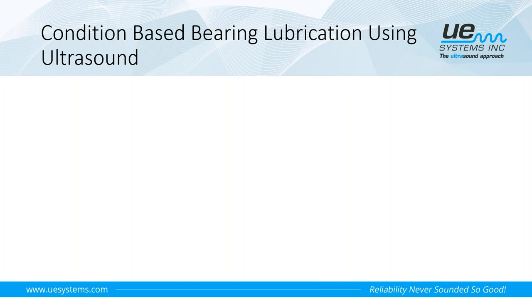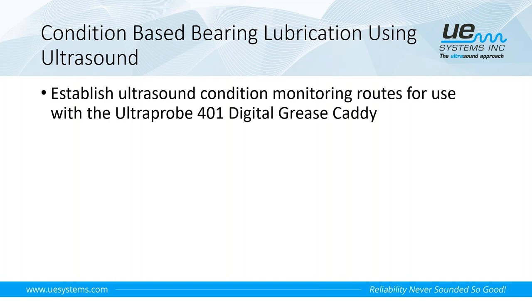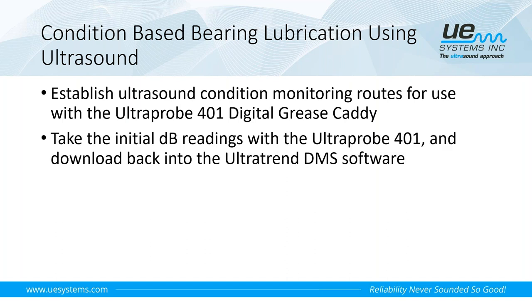Now, condition-based is going to be the best approach, and this is what you can do with the Ultraprobe 401. For those of you that have it or may have some interest, this is the scenario where you'll get the best results out of that digital grease caddy. It goes back to what we mentioned with the software, where we set up routes, and then we load that route into the grease caddy, go out and take our initial round of decibel level readings, and download that back into the software. Now, a better way to set your baselines, instead of letting the DMS software use the first reading that you download into it, is to use what's called the historical method. So we set up the route and begin to establish a dB trend or dB history on those points, and then we can select any reading that we want as the baseline.